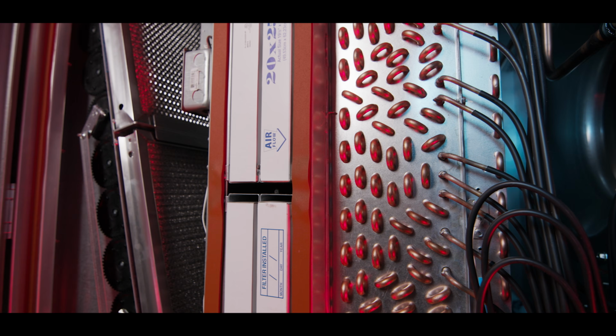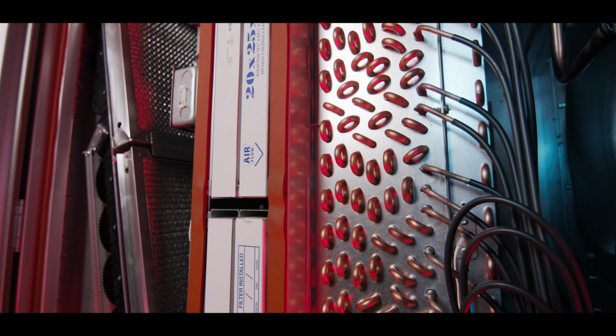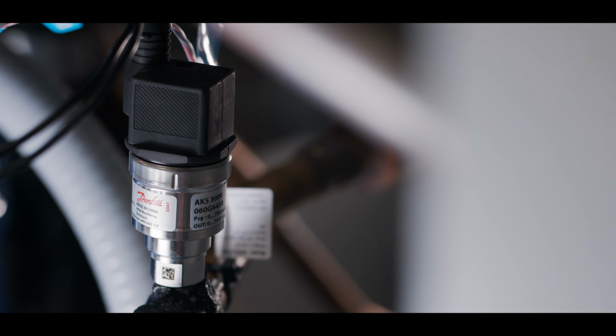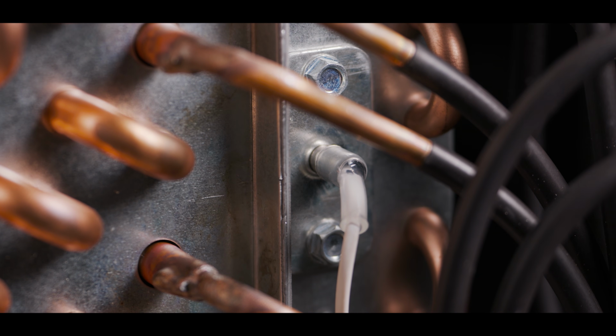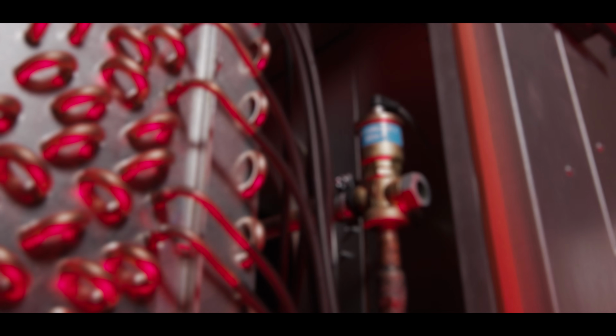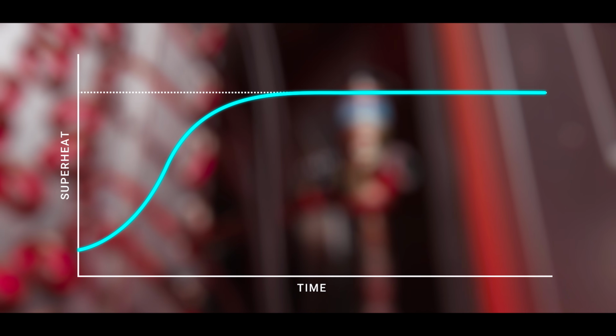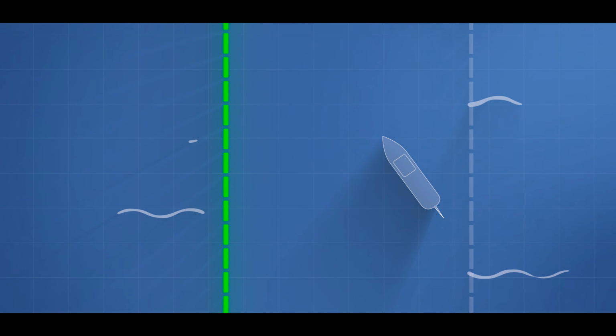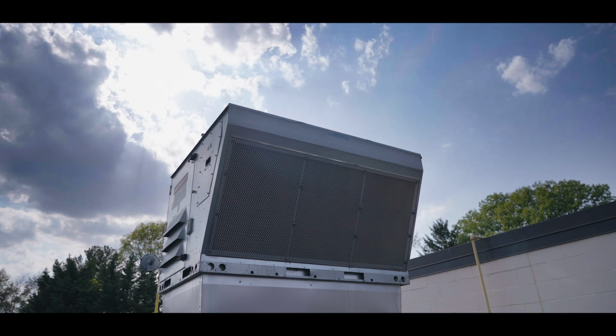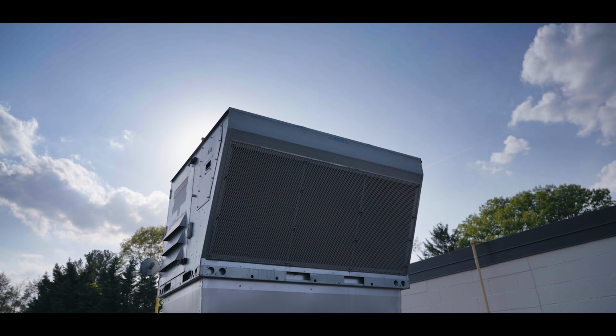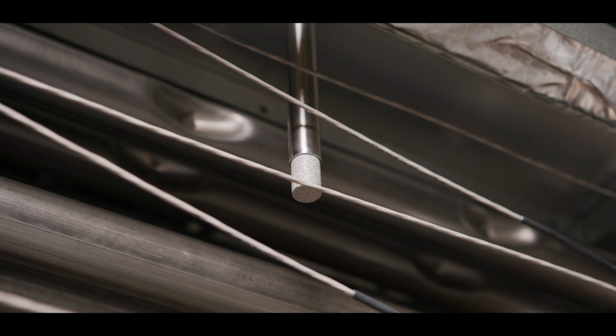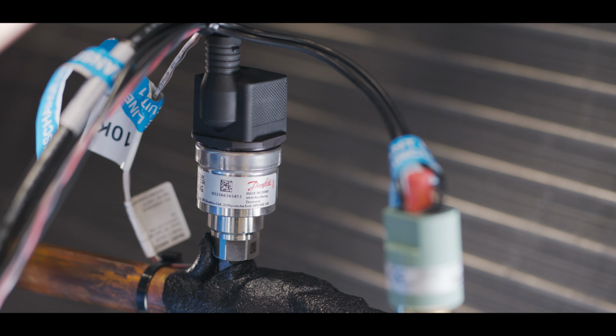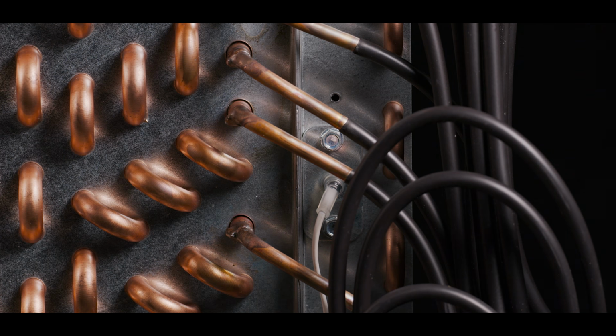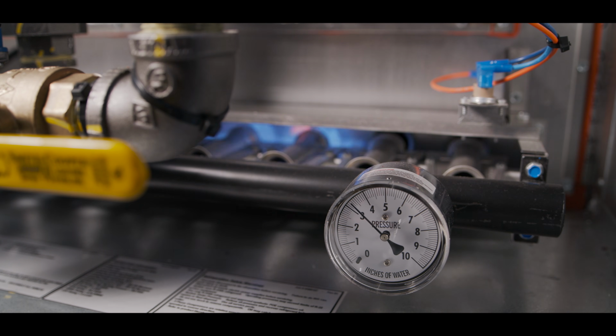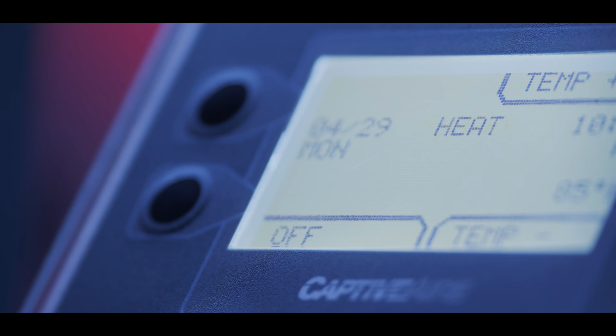For example, if, as Mike mentioned, we want to maintain a certain superheat, we'd need a pressure and temperature sensor at the outlet of the evaporator, a way to control superheat, and the right PID loop to smoothly steer us towards our target. Just like wind and currents affected how the ship steered, conditions around our units change constantly, so Paragon uses quite a few sensors to take all these variables into account in conjunction with finely tuned PID controls.